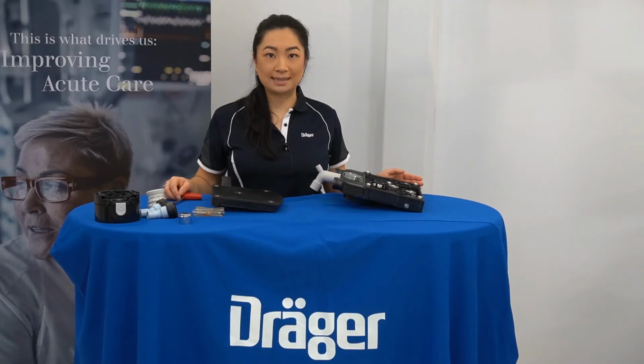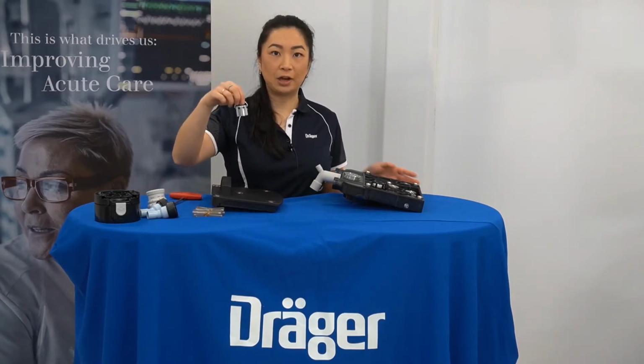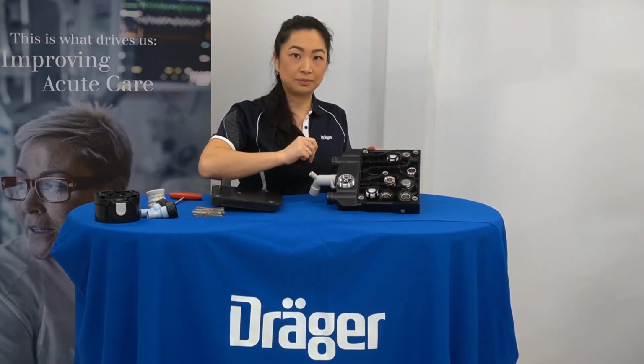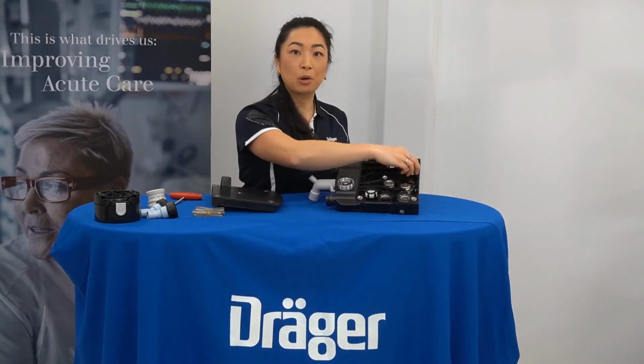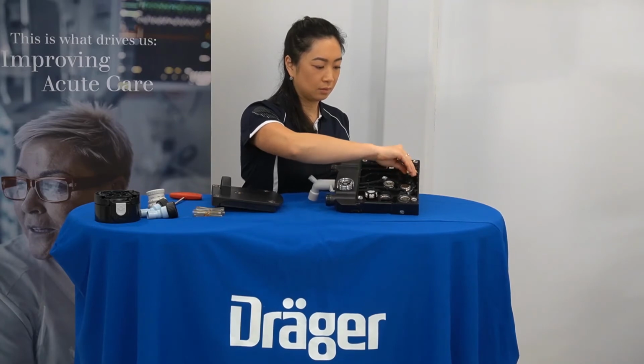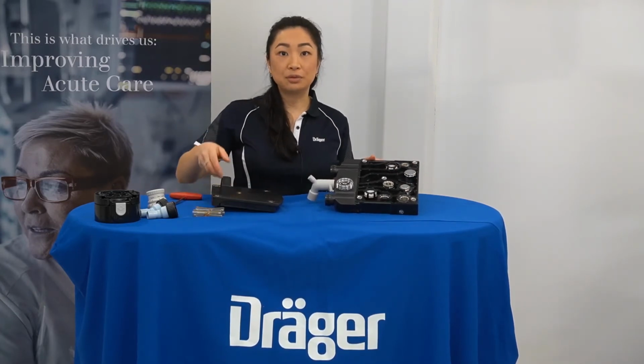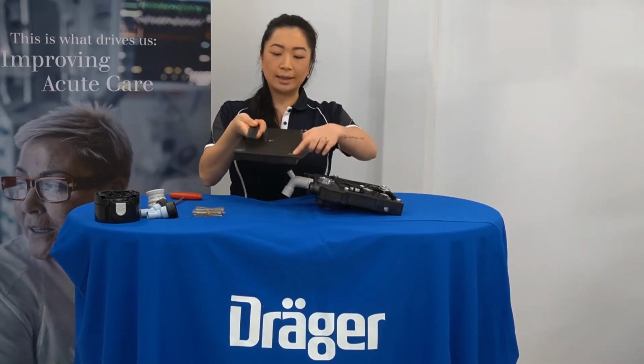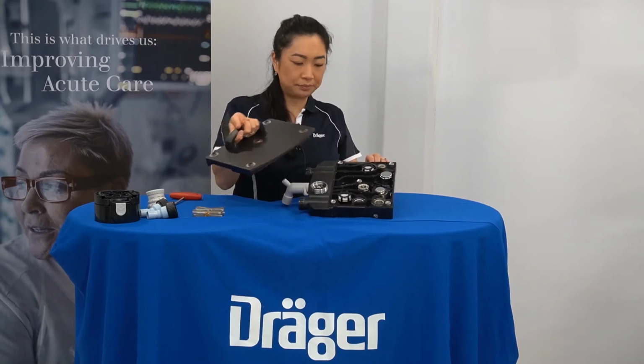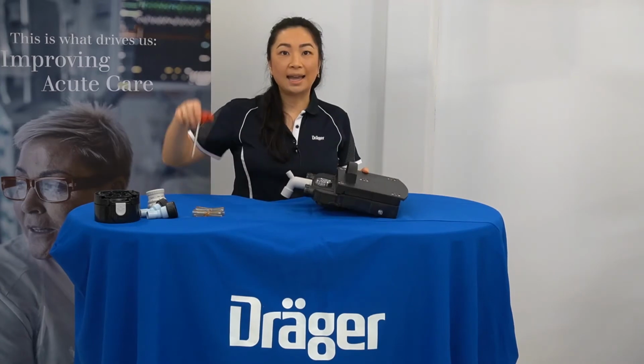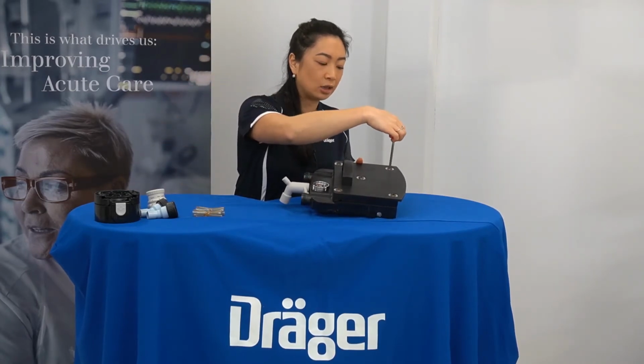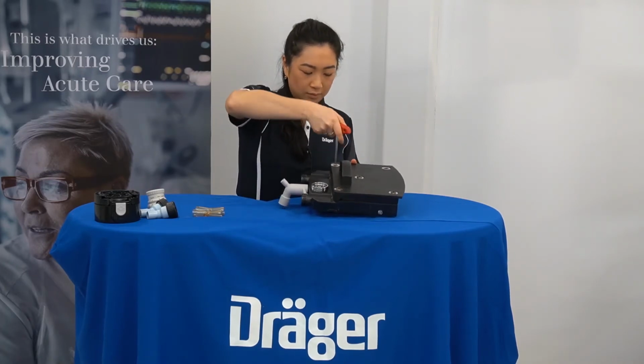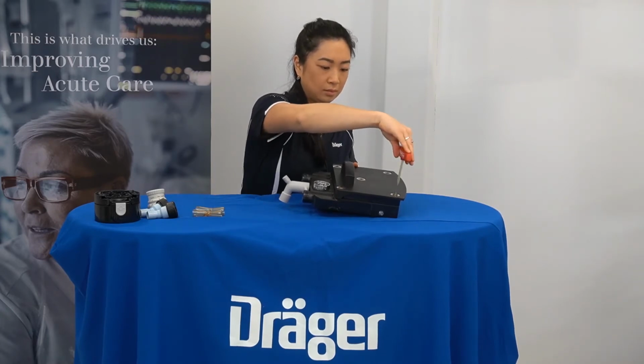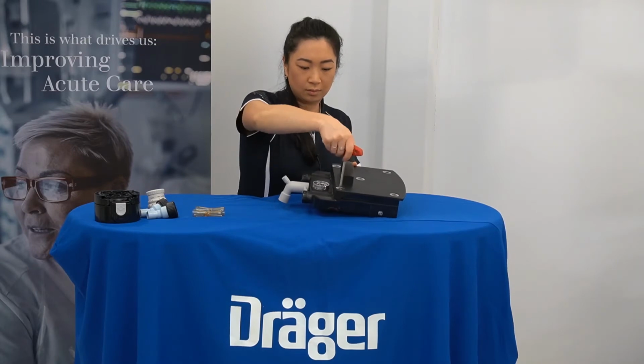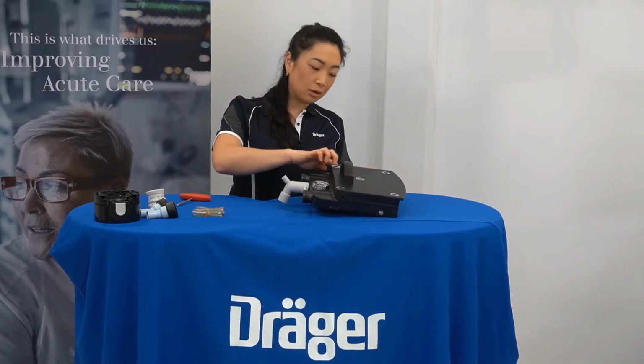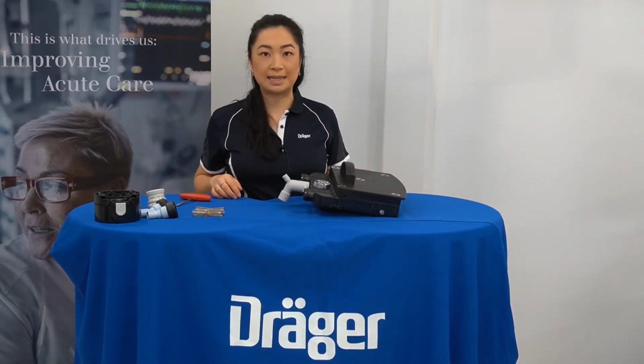To reassemble the breathing system, start by screwing on the additional air valve to this spot on the breathing system, ensuring that it is properly threaded. Then, to return the upper housing component of the breathing system, align the quick release screws with the screw holders. And take your screwdriver and, pushing down with a slight clockwise turn, lock the screws in. Ensure there is a proper seal between the upper component and the bottom component of the breathing system.